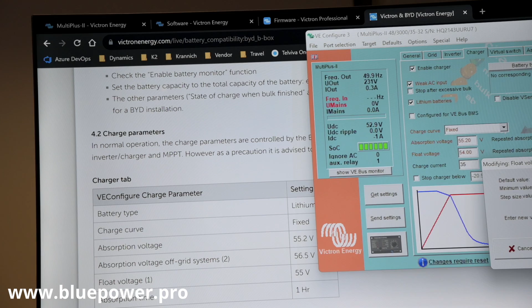On absorption voltage, we can see that BYD recommends 55.2 volt for an ESS system, and absorption for an off-grid system is slightly higher. But we've got a grid connected system, so we can just set that to 55.2. We've got our float voltage, also indicated, so we can make that 55. And our maximum absorption time is 1 hour, so that's also a recommendation for lithium.